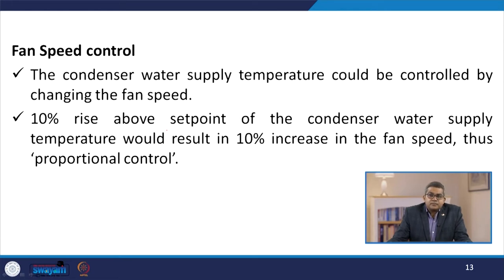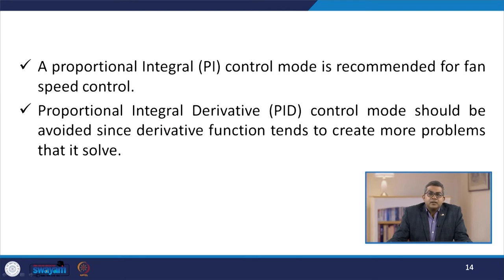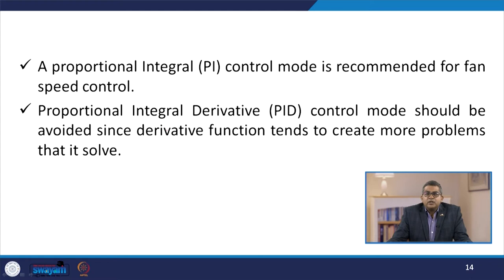Fan speed control: the condenser water supply temperature can be controlled by changing the fan speed. A 10 percent rise above the set point of condenser water supply temperature would result in a 10 percent increase in fan speed — proportional control. A proportional-integral, or PI, control mode is recommended for fan speed control. The PID control mode should be avoided, since the derivative function tends to create more problems than it solves.